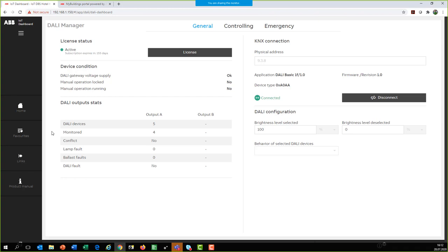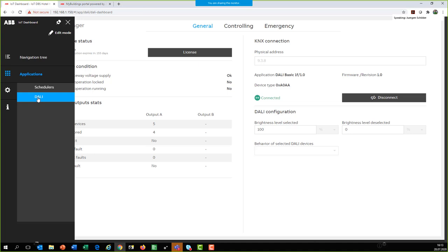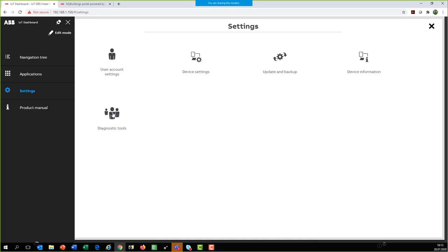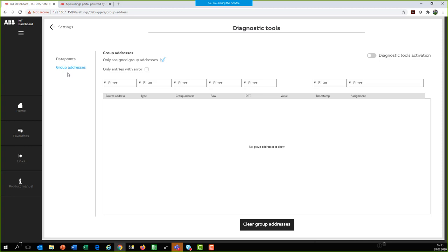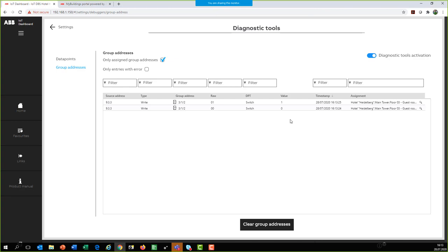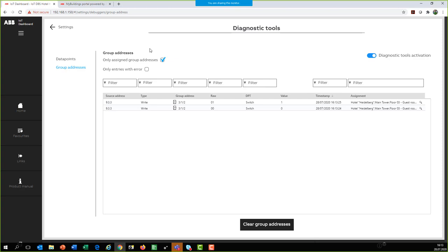The last nice feature is the diagnostics tools. Under 'Diagnostics' in the dashboard, we can record telegrams like in the group monitor. Click 'Group Addresses', activate it, and when you press a rocker, the group telegram is stored showing: source address, command value, group address, value zero or one, data point type (switch), timestamp, and text description — similar to the group monitor.